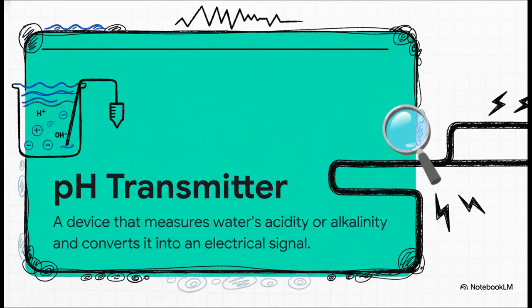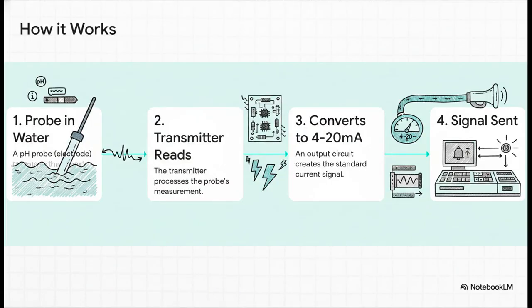Its job sounds simple, but it's absolutely crucial. It measures the water's pH, how acidic or alkaline it is, and it turns that chemical property into a simple electrical signal. Here's how it works in a nutshell. You have a probe, an electrode, just sitting there in the freshwater line, constantly sensing the pH. The transmitter reads that measurement, and then, this is the clever part, an output circuit converts it into a very specific electrical current, a 4 to 20 milliamp signal. That signal then gets sent directly to the engine control room.